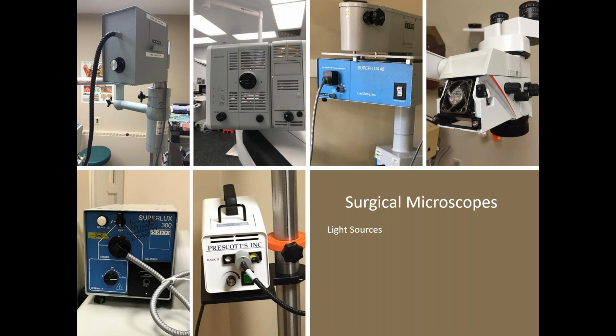But the next one is a xenon halogen split. A lot of eye doctors, depending on the case, will use a halogen light source, but if they have the same scope, they'll use the xenon for a different case. So that's common in more eye scopes, or even in some ENT doctors will have that, and halogen will be the backup. The next one is an older xenon light source. It's a Super Lux 40. There's a Leica. That's a small LED that's built inside their ENT head, or it could be a dental head.